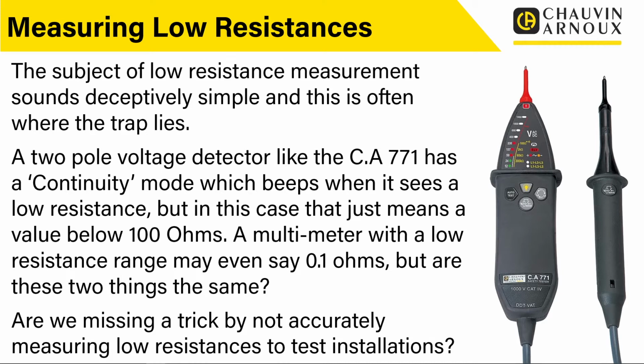And I think there is an argument, the more you look at this, to say that in a lot of scenarios it would be very useful information for us to carry out true low resistance measurements, because we can check connections, we can see deterioration, we can see corrosion and all these things. In many cases we might just go, yep, quick beep with a multimeter and say, yeah, that's fine. And actually if we checked it with a proper low resistance ohm meter or micro ohm meter, there might be a lot more data there that we're missing. So I think sometimes by just conflating all these things together, we really do miss a trick.